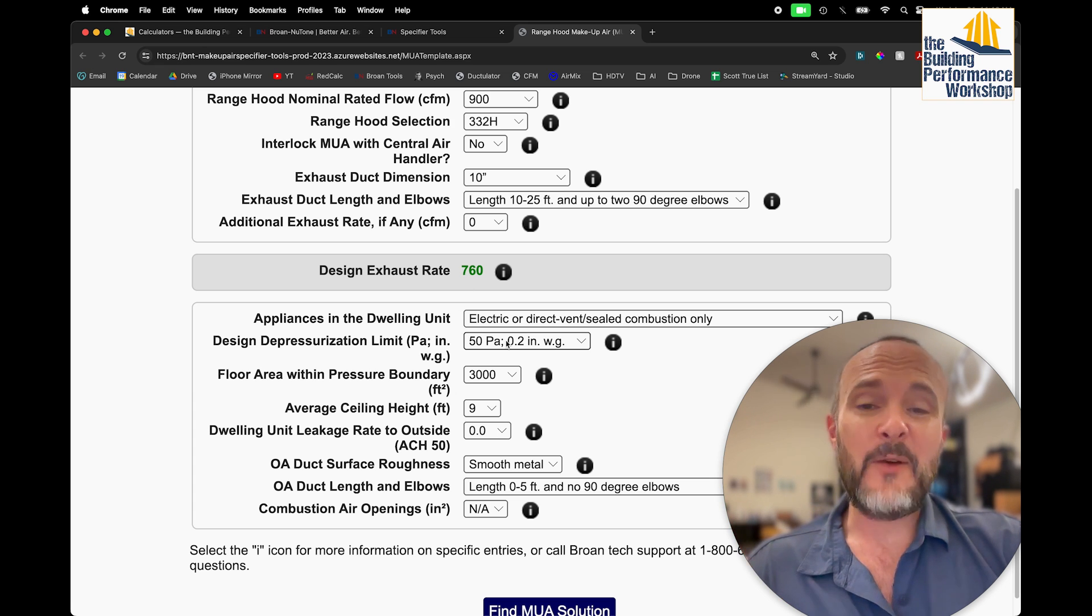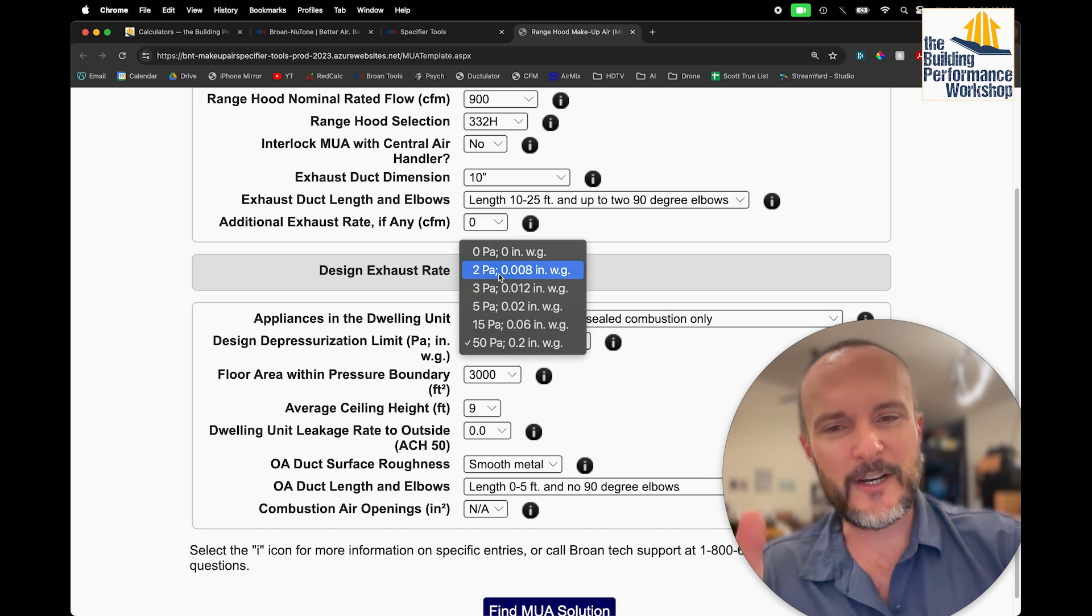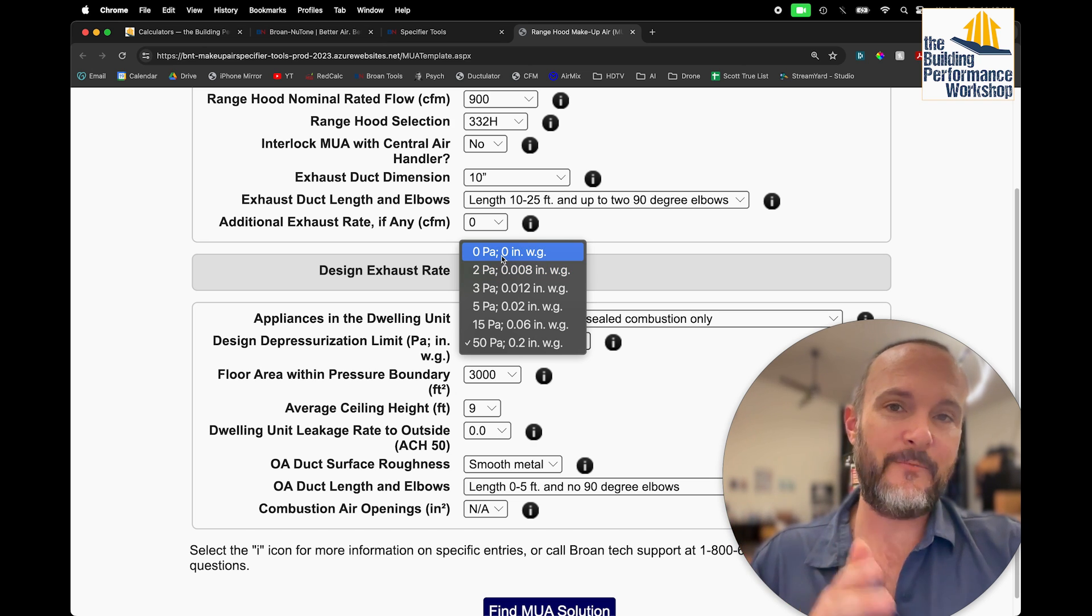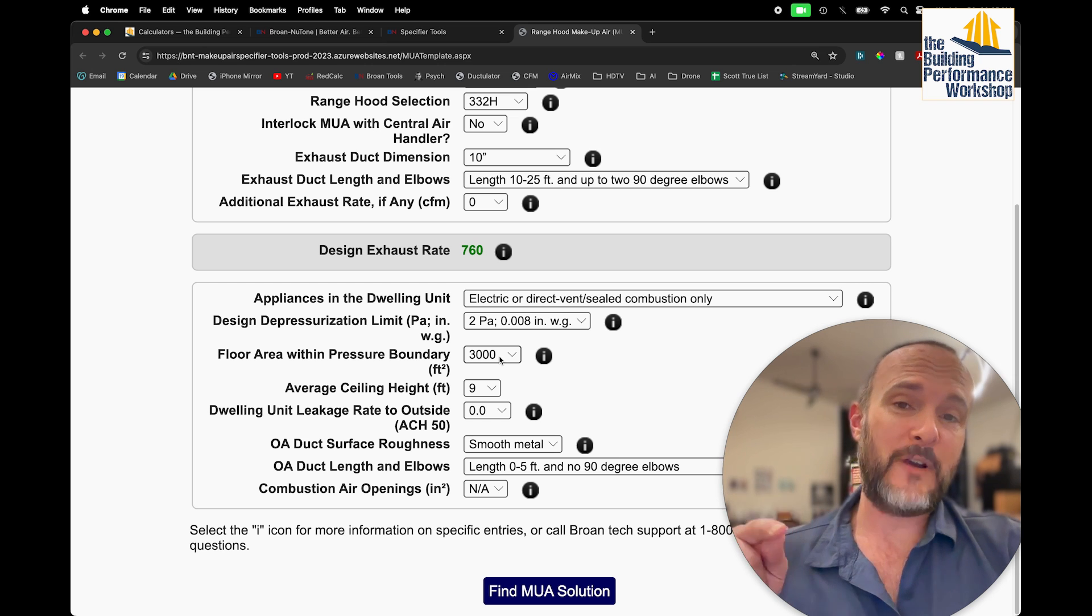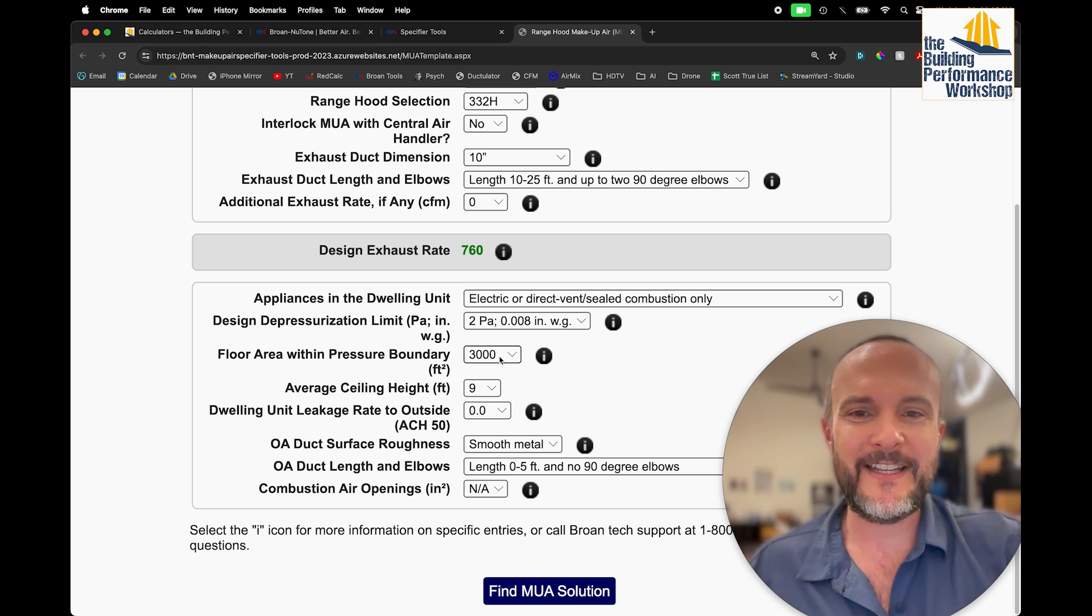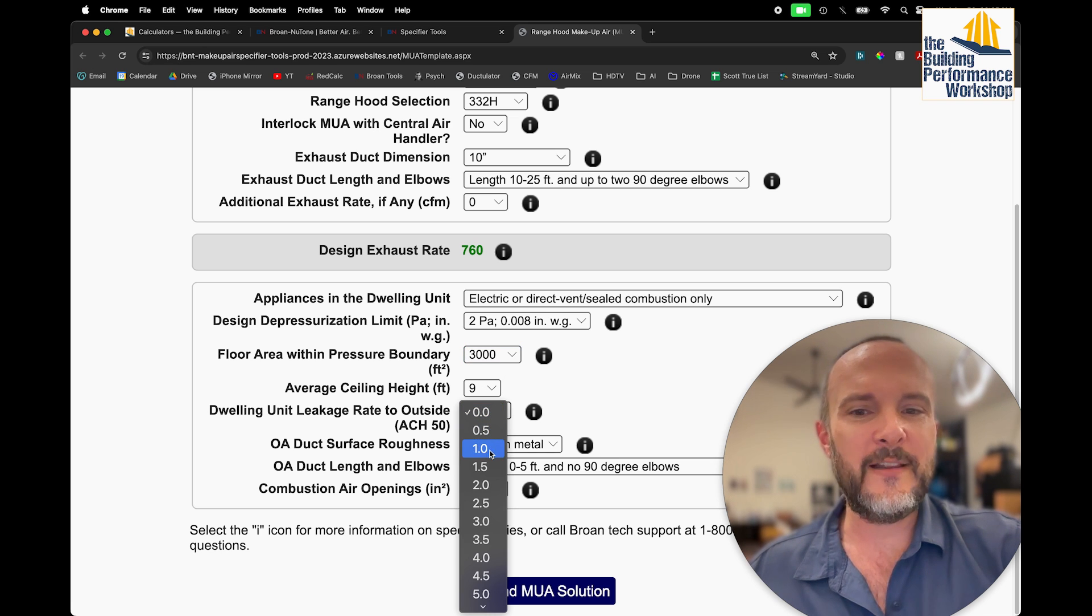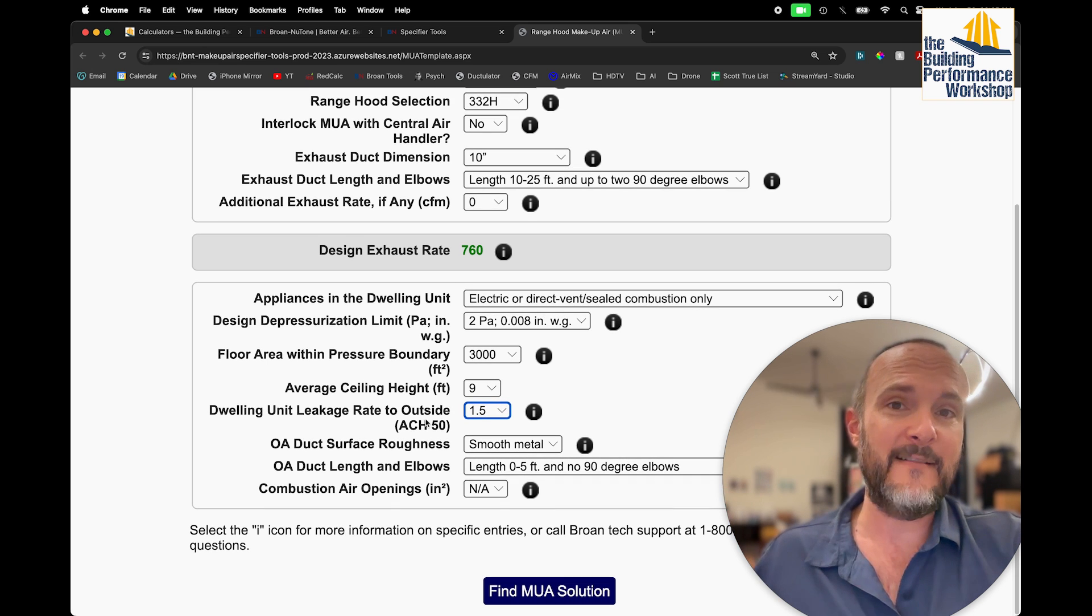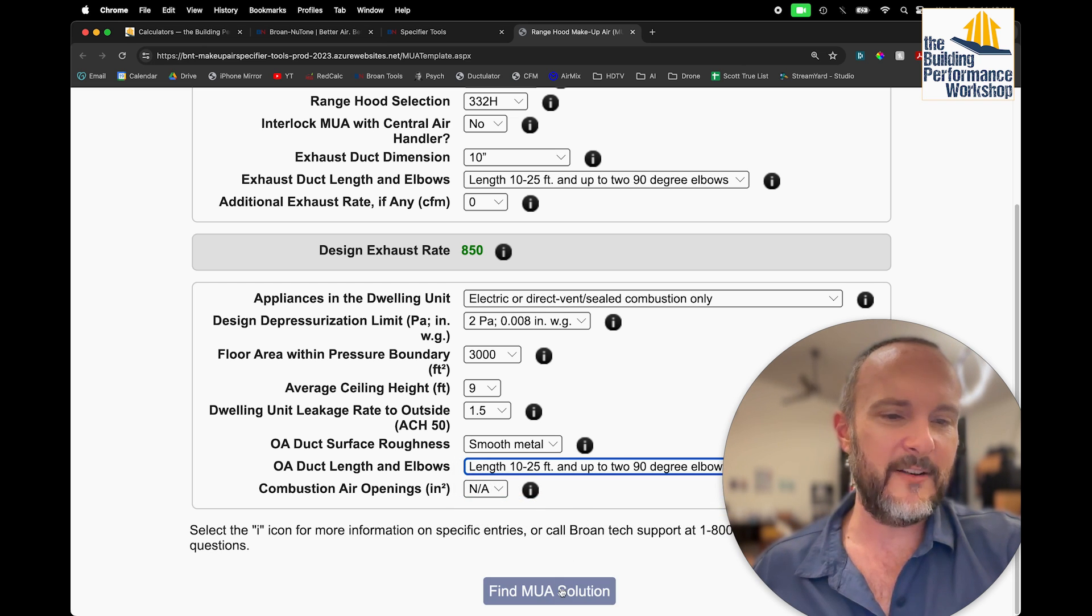With my depressurization, I want to keep my depressurization as minimal as possible. If I'm trying to build high performance, you don't want to mess around with pressure effects. So let's try and shoot for 2 pascals. You can't shoot for zero, because that's impossible. With a passive makeup air system like this, 2 pascals is the most that you can get out of it. And by the way, 2 pascals is enough to backdraft a wood-burning fireplace. So if you have one of those, or gas-powered, as long as it's connected to the inside, you're going to be backdrafting that, even when you're using the makeup air. We've got our 3,000 square feet. We've got 9-foot ceilings. We're going to put our leakage at 1.5 ACH-50, because that's actually what my builder says that he can achieve, not 3, like Broan was saying earlier. And then my makeup air length is going to be, again, 10 to 25 feet with two 90-degree elbows to get it where it needs to go.